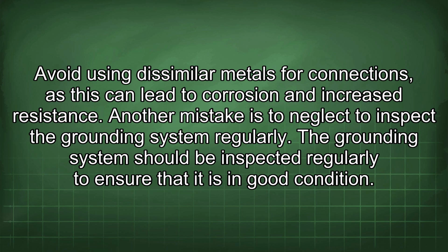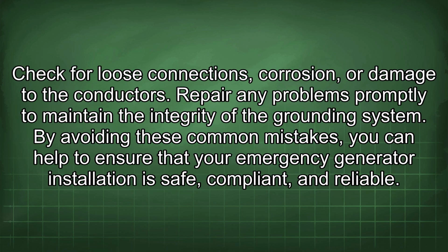Another mistake is to neglect to inspect the grounding system regularly. The grounding system should be inspected regularly to ensure that it is in good condition. Check for loose connections, corrosion, or damage to the conductors. Repair any problems promptly to maintain the integrity of the grounding system. By avoiding these common mistakes, you can help to ensure that your emergency generator installation is safe, compliant, and reliable.